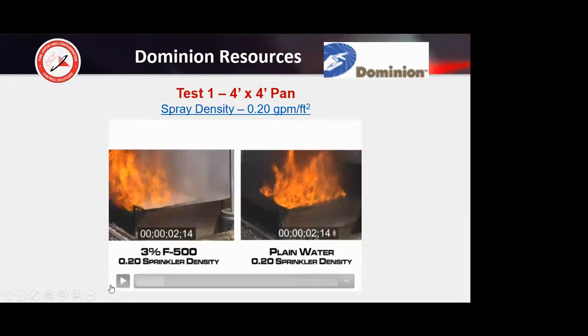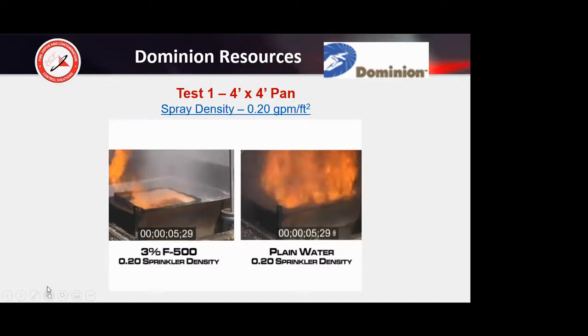So at this point, we have a thermal imaging camera, and once we reached 1100 degrees, the systems were manually put on. We ran all of the plain water tests in a row, 0.15, 0.2, 0.3, 0.4, before we added any agent, because we know that with F500, once you put it in your piping system, you might have a little residual. So we didn't want any impacts of that. So anyways, here we're seeing the plain water at 0.20.